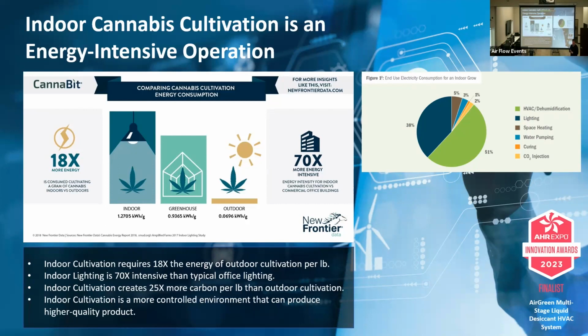New Jersey looks like it's poised to be oversupplied. I think Michigan already is. And so our advice to growers is invest in energy efficiency. That's the only real way to create a sustainable competitive advantage. If you look here, almost 90% of their energy use is either HVAC or dehumidification and running the lights. So sometimes it lends itself to CHP. That's our point: if you tie in CHP with a liquid desiccant system, you can cut your costs significantly.